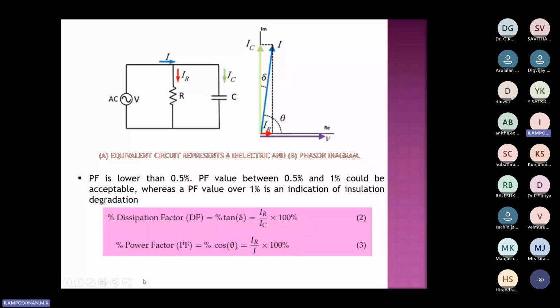That means, if you look at the right hand side, I hope my arrow and pointer are visible to you. Okay. So here, if it is completely capacitive, then the voltage and capacitive current are out of phase, that means 90 degrees off. When there is both resistive current and capacitive current, you have a smaller resistive component, meaning your current is not completely capacitive, but it is a phasor sum of IC and IR. So you will have a small angle between the ideal capacitive current IC and your real current I.